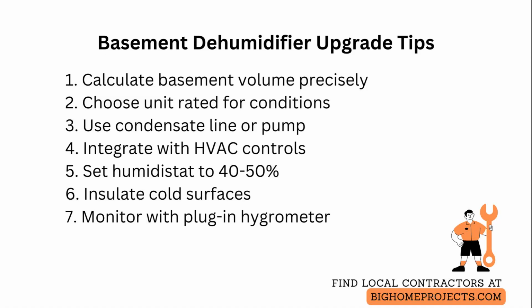Integrate the dehumidifier with the heating, ventilation, and air conditioning control system, or use a dedicated humidistat set between 40 and 50% relative humidity for optimal mold prevention without over-drying. Insulate cold surfaces such as ductwork, foundation walls, and exposed pipes to reduce condensation that can overwhelm the dehumidifier.